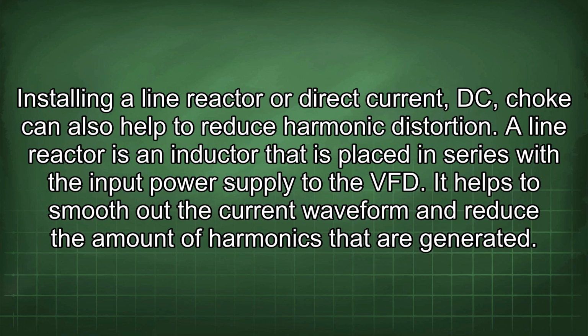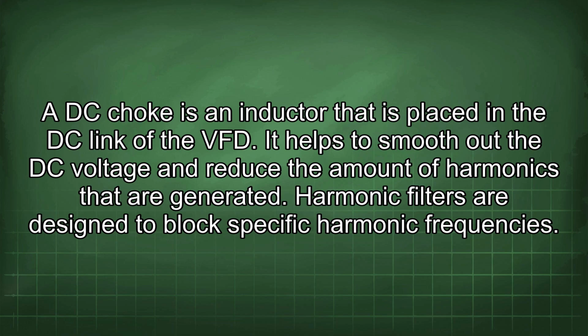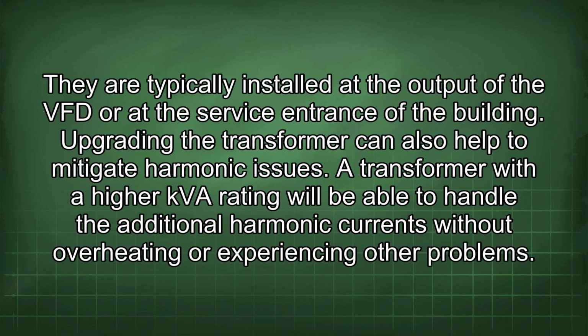A line reactor is an inductor that is placed in series with the input power supplied to the VFD. It helps to smooth out the current waveform and reduce the amount of harmonics that are generated. A DC choke is an inductor that is placed in the DC link of the VFD. It helps to smooth out the DC voltage and reduce the amount of harmonics that are generated. Harmonic filters are designed to block specific harmonic frequencies. They are typically installed at the output of the VFD or at the service entrance of the building.